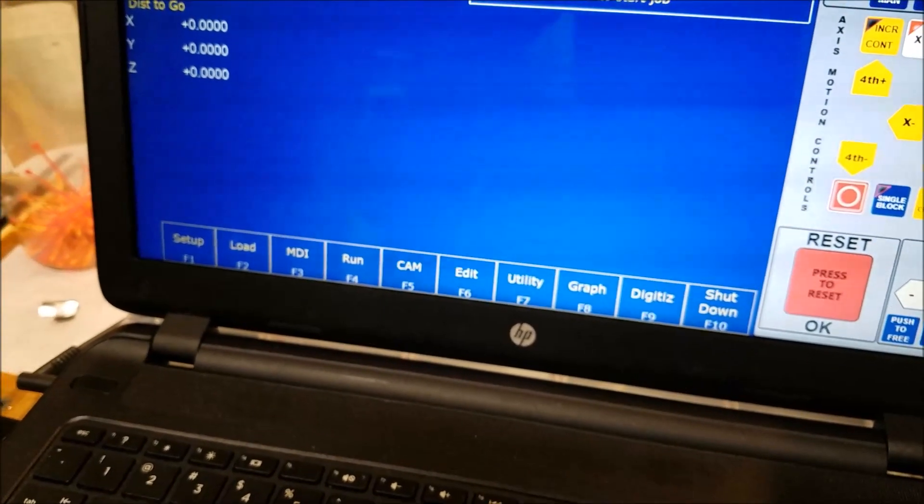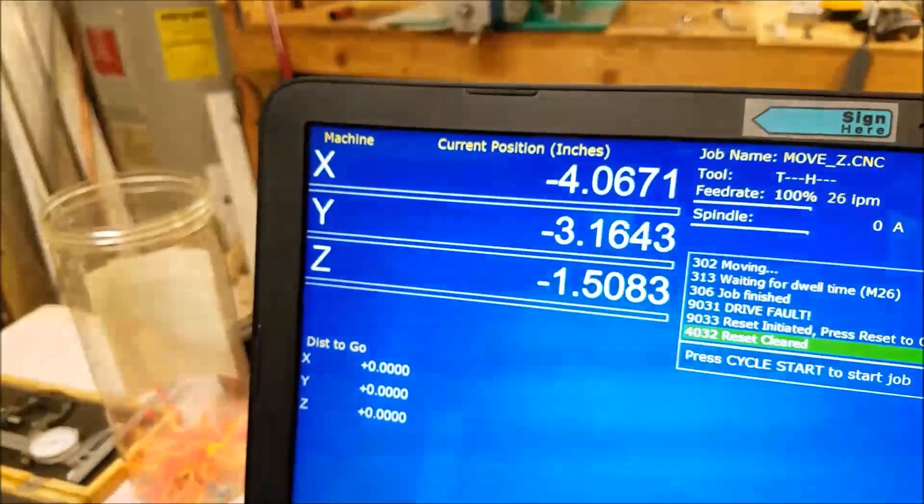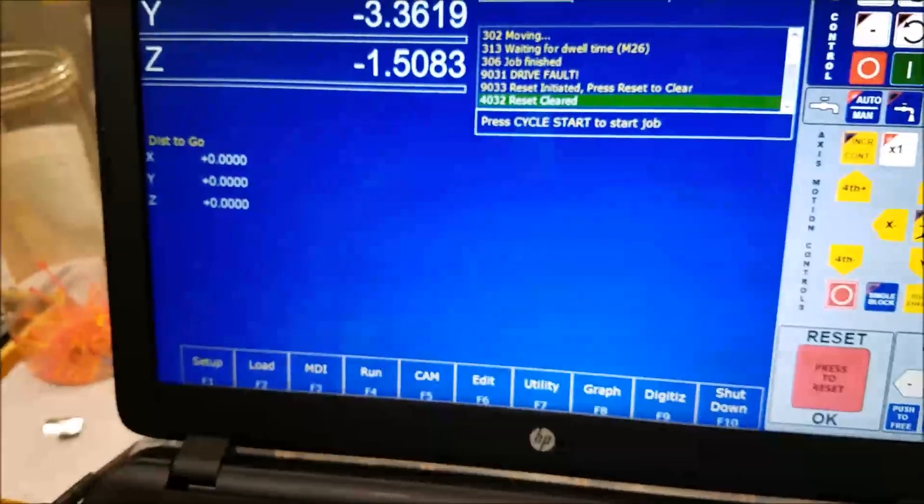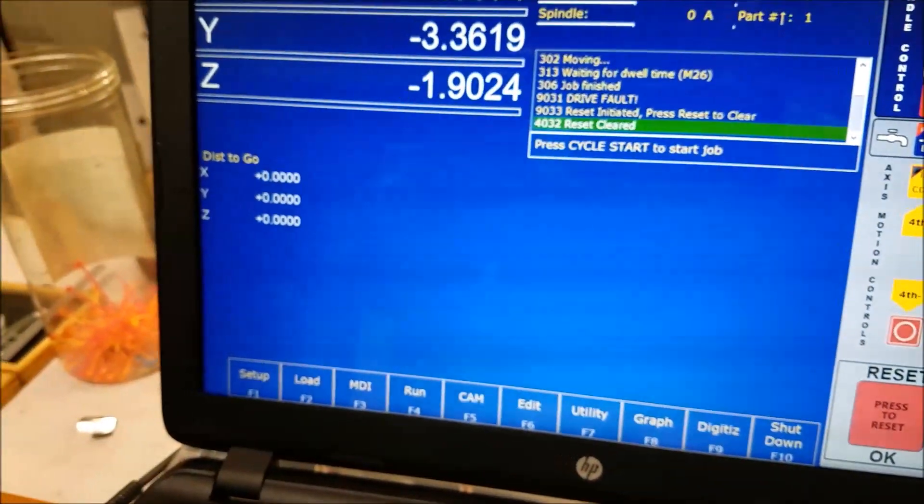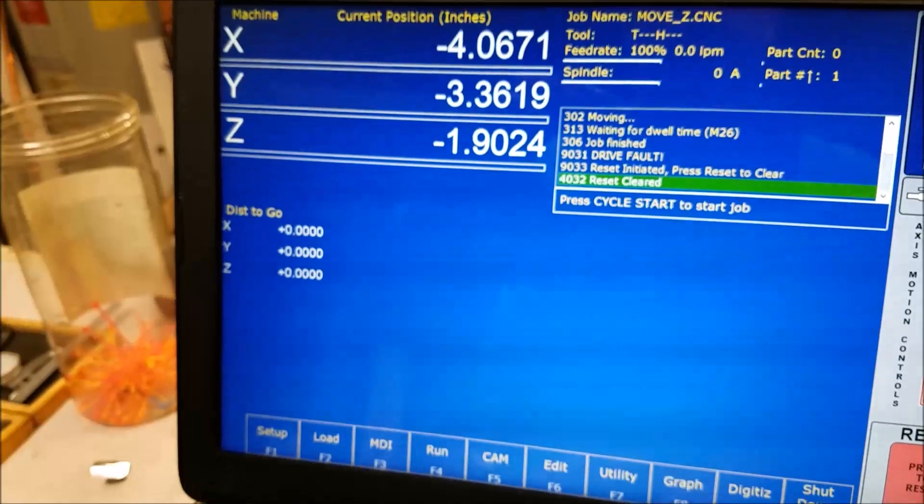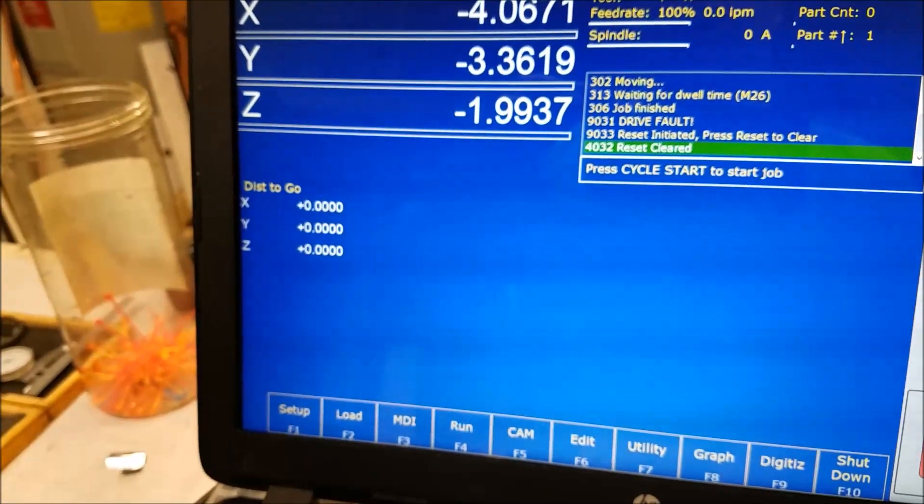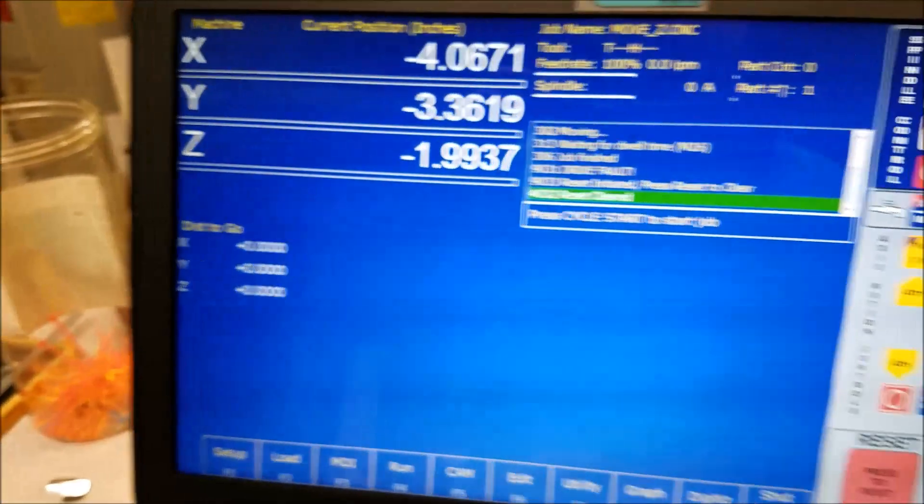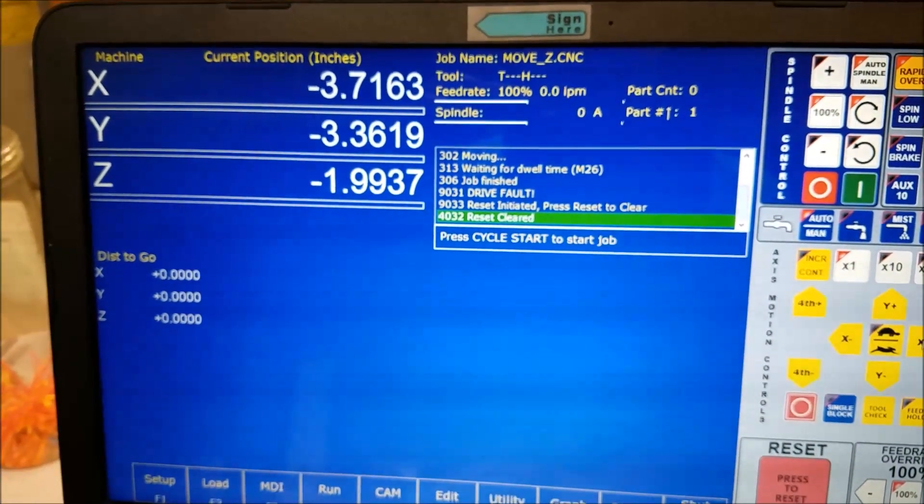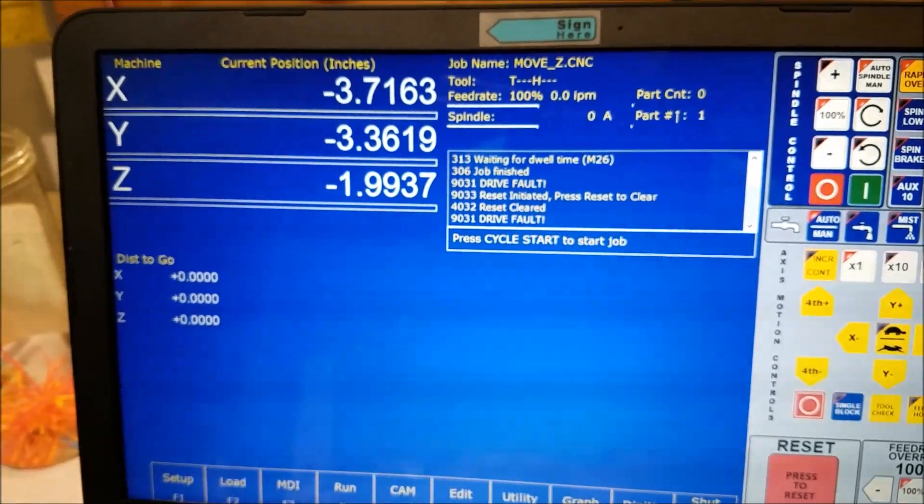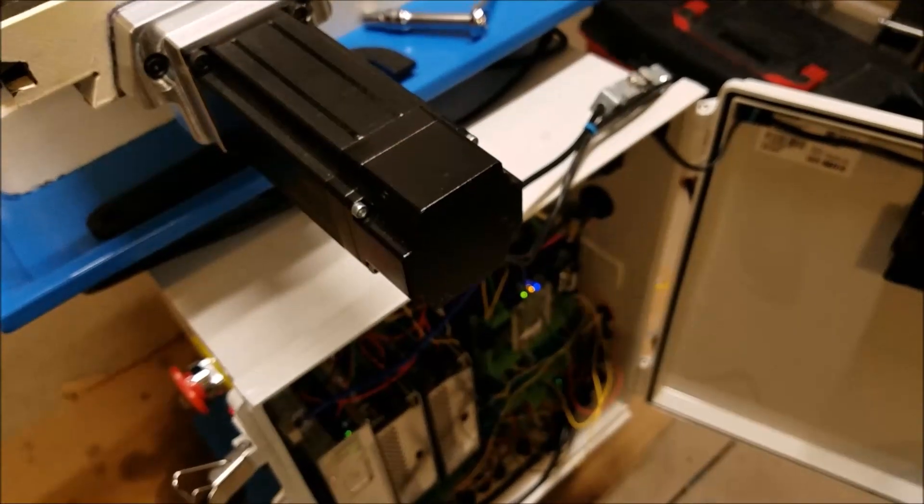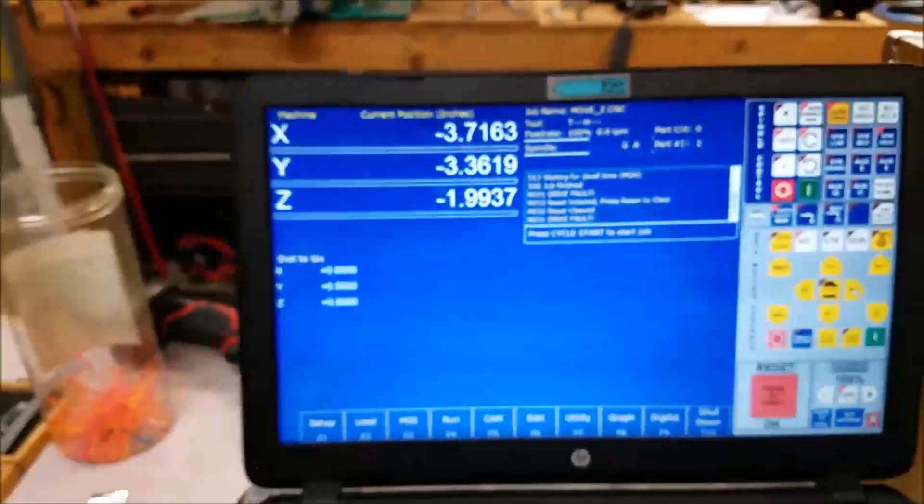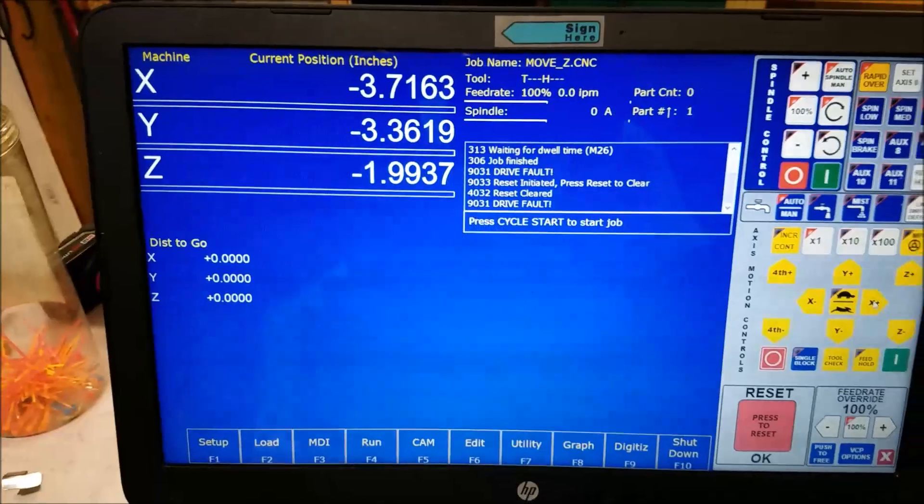Now I can press reset right now and clear that alarm. And now I can move my axes again. I can move Y, I can move Z, but guess what happens when I go to try to move X again? Boom, drive fault. So that's good. That's a good safety measure. So I think that kind of demonstrates how this functions.